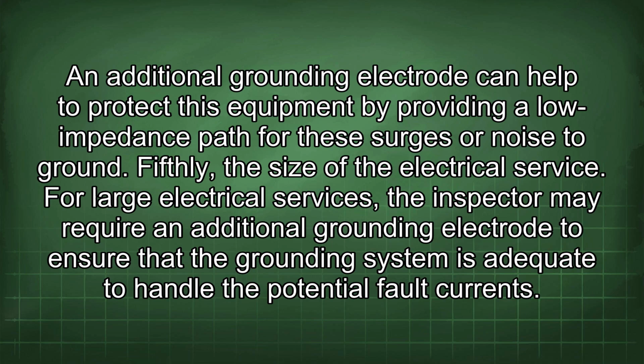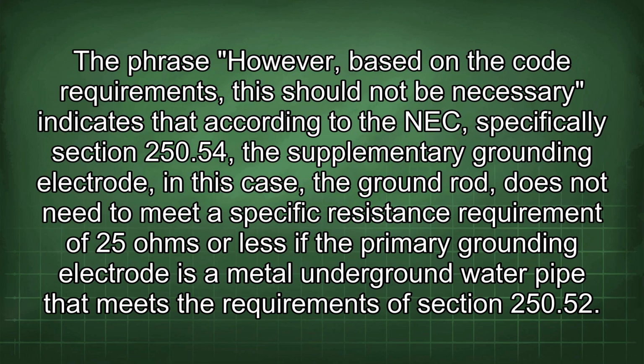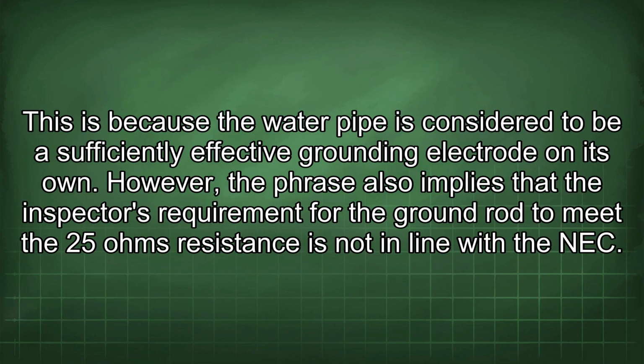For large electrical services, the inspector may require an additional grounding electrode to ensure that the grounding system is adequate to handle the potential fault currents. The phrase, "however, based on the code requirements, this should not be necessary," indicates that according to the NEC, specifically section 250.54, the supplementary grounding electrode, in this case the ground rod, does not need to meet a specific resistance requirement of 25 ohms or less if the primary grounding electrode is a metal underground water pipe that meets the requirements of section 250.52.